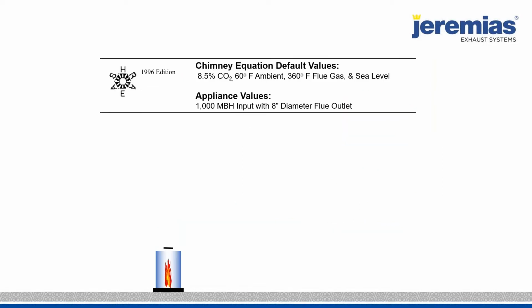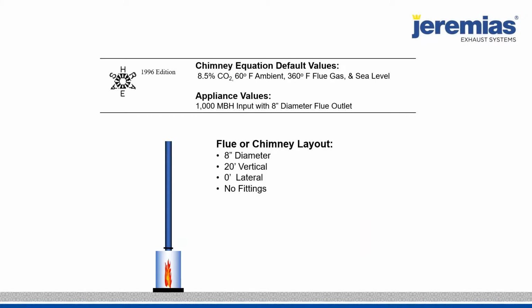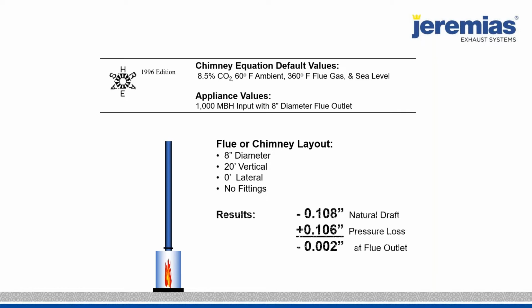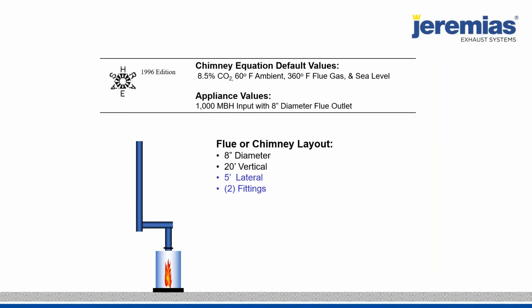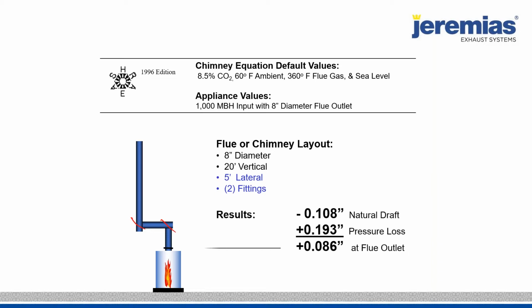So I want to show you just a quick example on how the factory chimney people look at these systems. So let's say we start with a UL listed tank heater, and they like to see a slight negative pressure at the outlet. They ship it on the job site with an 8-inch diameter outlet, so the 8-inch outlet right here. And by the way, they test it with a 20 feet vertical tall stack at the factory. So let's say we have a couple fittings. We do the calculation. We see that you do the math, and we say positive vent pressure at the outlet.